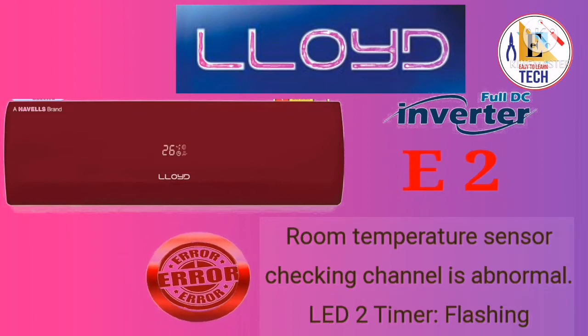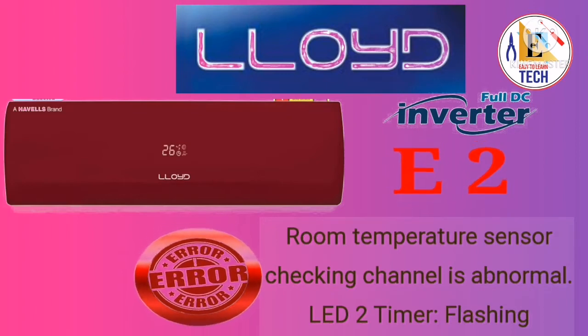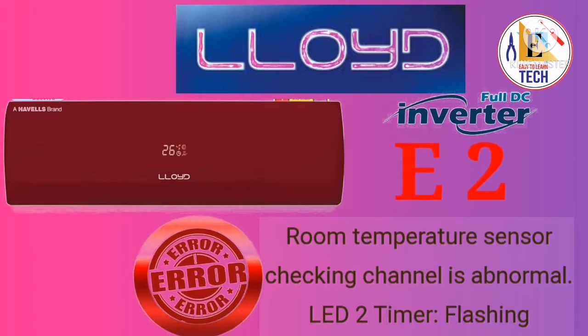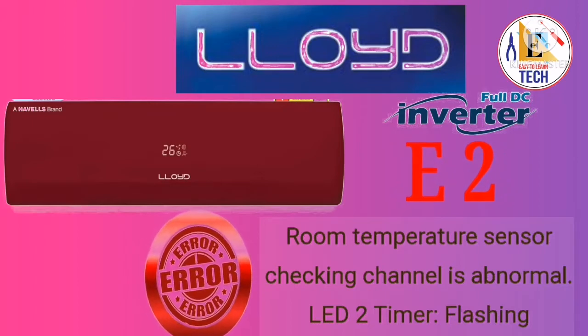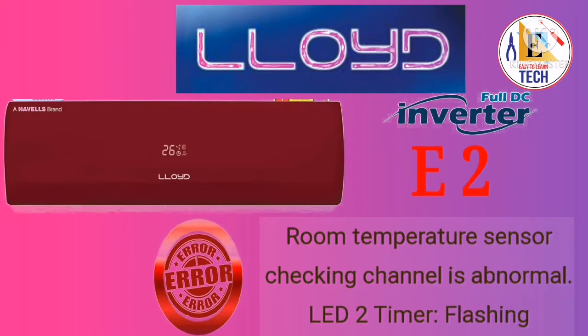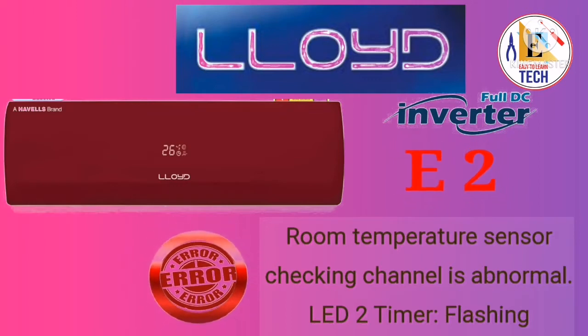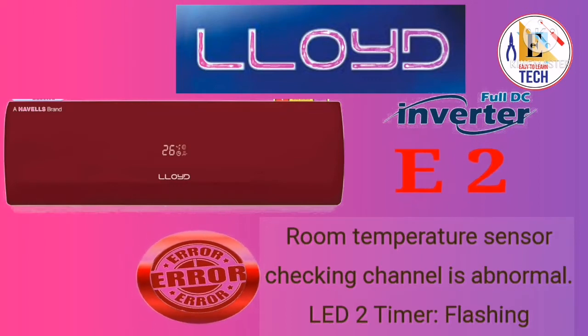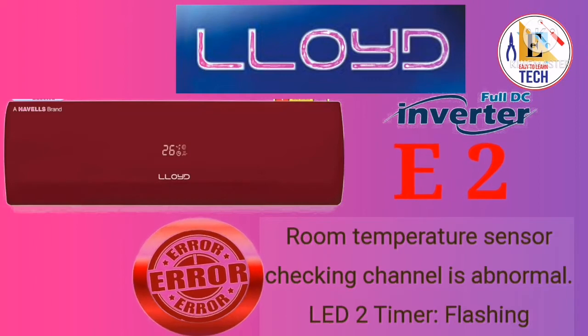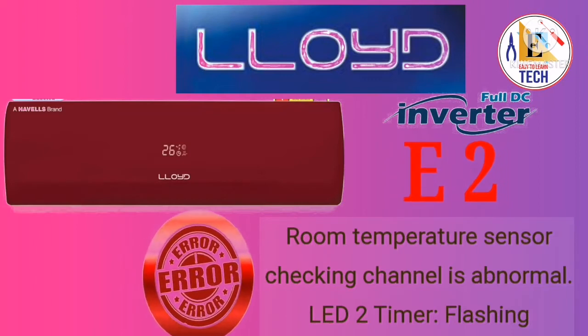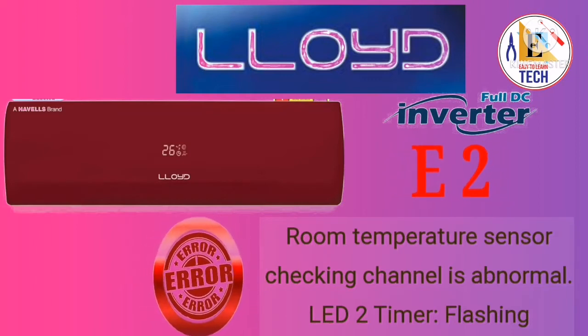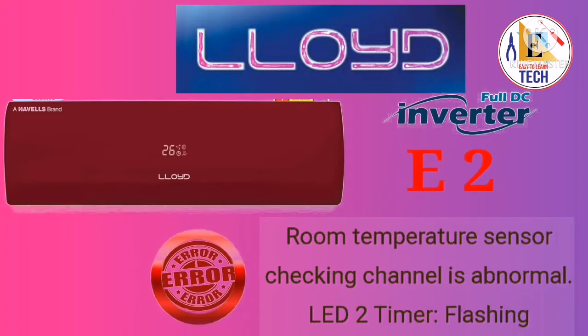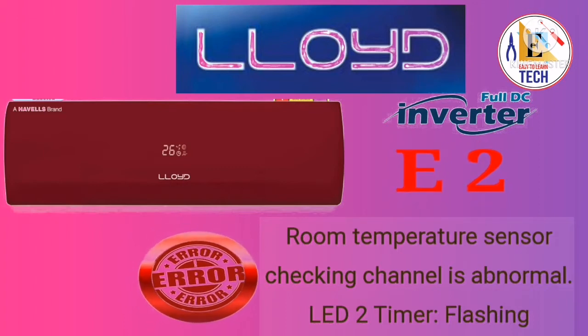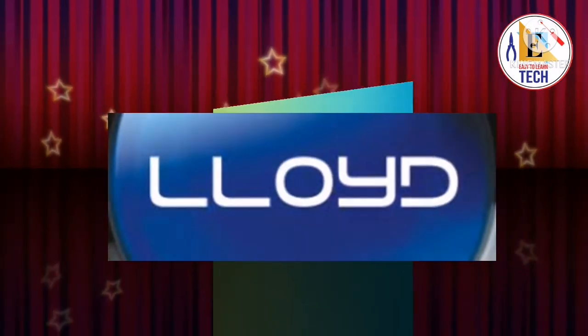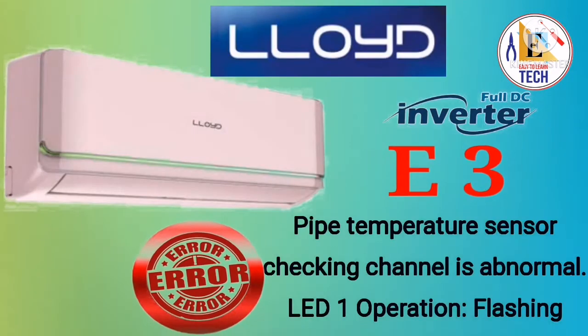Then you have to check the resistance of your room temperature sensor. If the resistance is good, it means your room temperature sensor is good. Then you have to check the PCB, whether the output supply from the PCB is coming to the room temperature sensor or not. If it is not coming out from the PCB, then you have to change the indoor PCB board. Then your error E2, LED2 timer flashing, will be off and your unit will be in working condition. See the next error code.